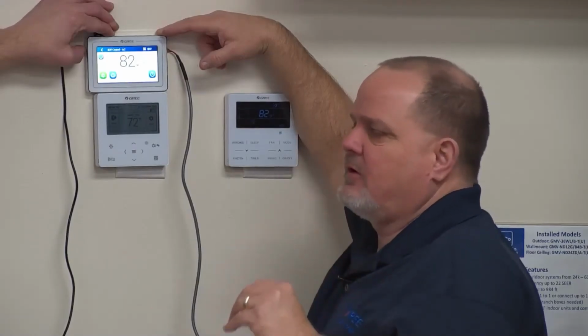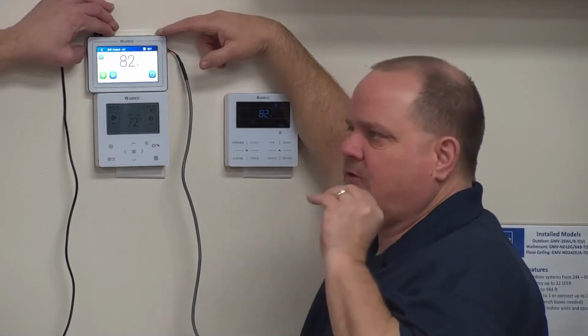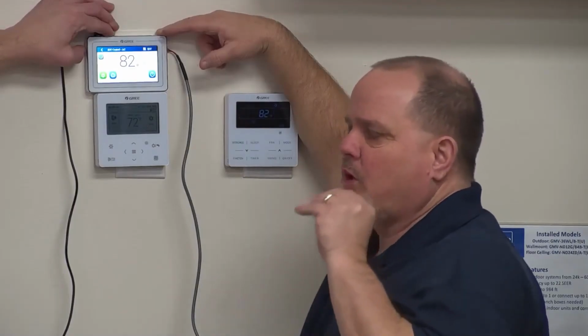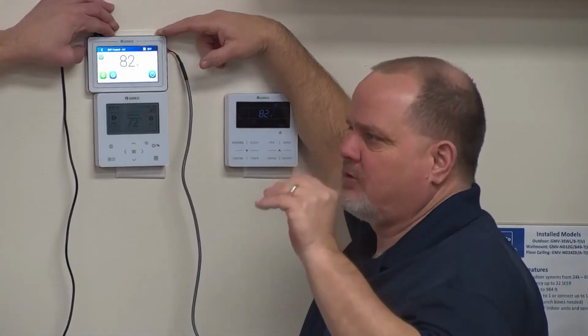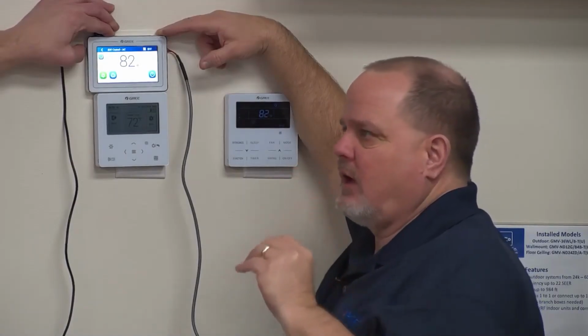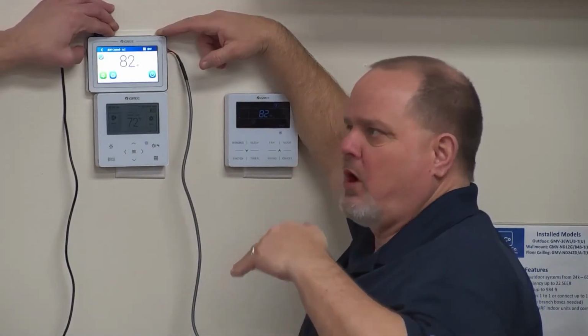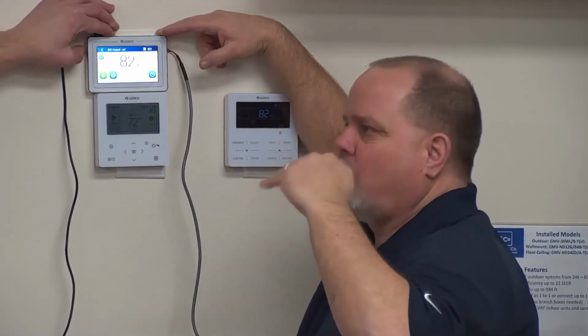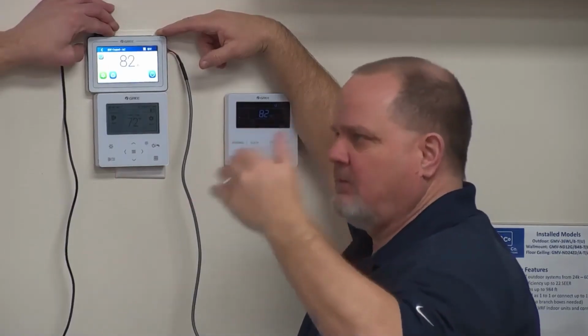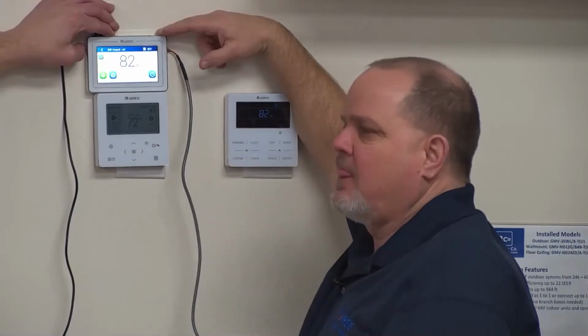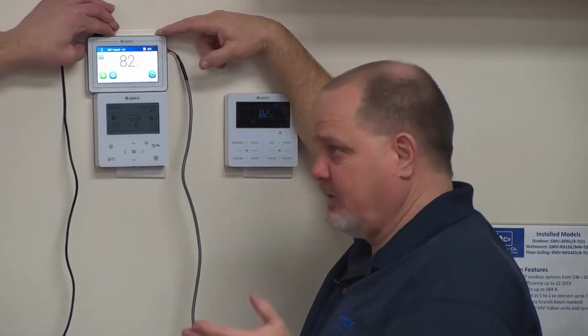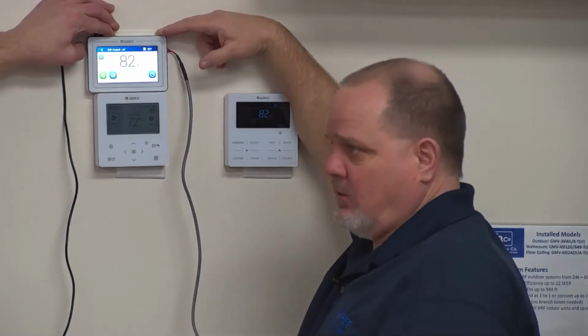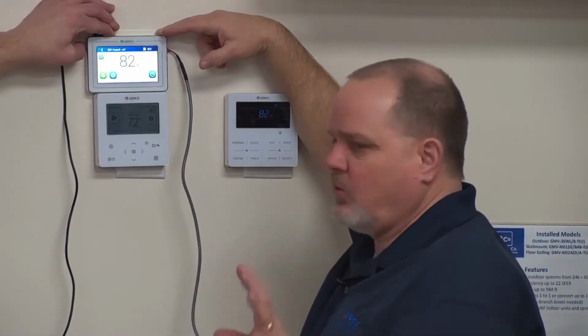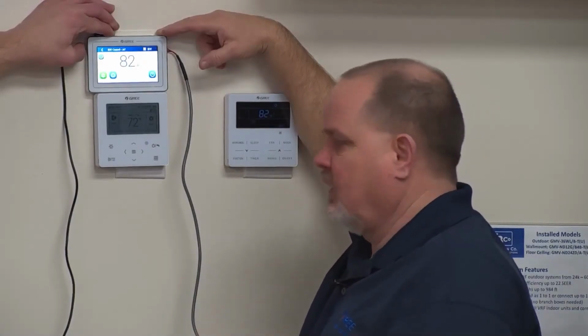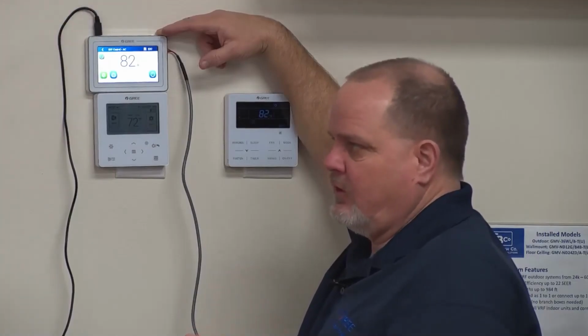And let's say you've got a 3-ton. So it's going to try to achieve 1200 CFM regardless of the static pressure on the machine. So if you've got high static, that blower motor is going to ramp up even harder, trying to overcome that static to keep delivering that 1200 CFM. Whether the motor can actually do it or not is a different story, depending on the ductwork and stuff like that. That's not the way variable speed MultiPRO works, or any inverter-driven unit.